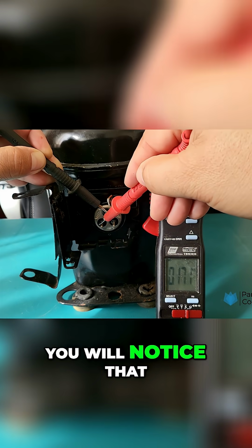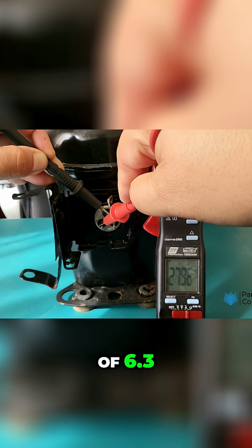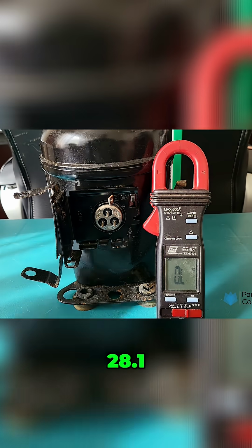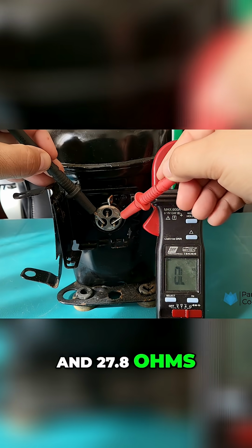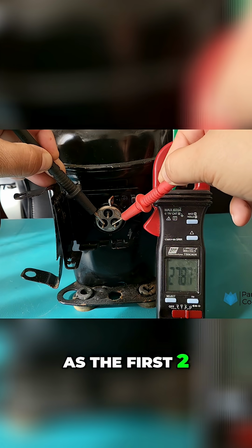As we go through the resistance test on the windings, you will notice an inconsistency with the readings. We are getting values of 6.3, 28.1, and 27.8 ohms, respectively. That constitutes a failed test, as the first two values don't add up to make the third.